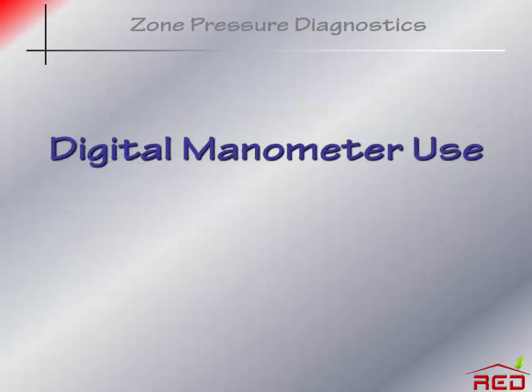I want to talk a bit about the use of your digital manometer or manometers for ZPD. You need a digital manometer for a non-modifiable zone and for modifiable zone analysis. In each case, you must measure pressure differences across pressure boundaries.